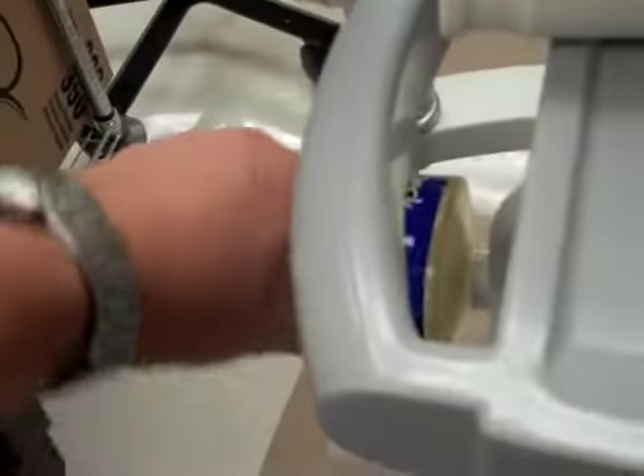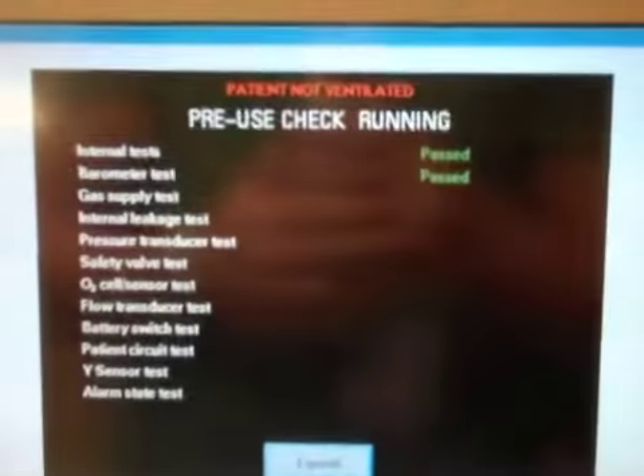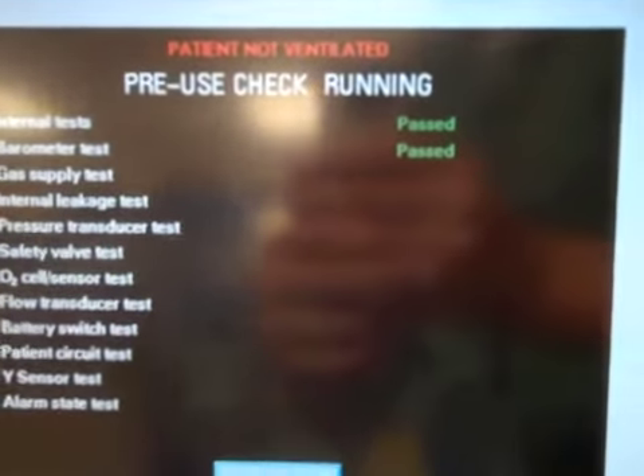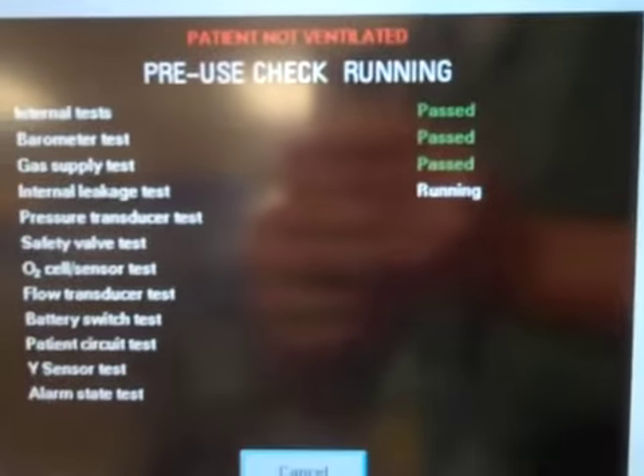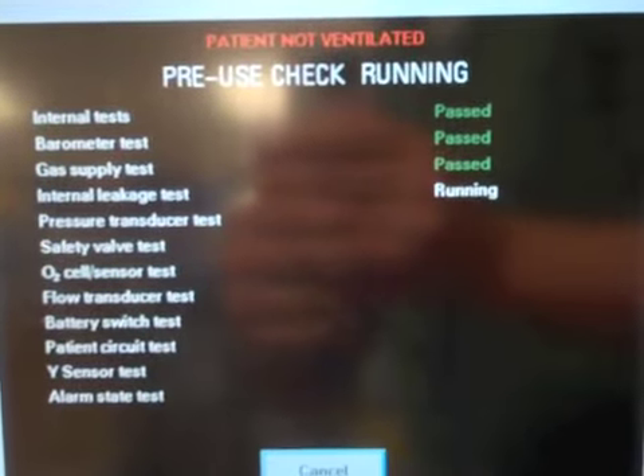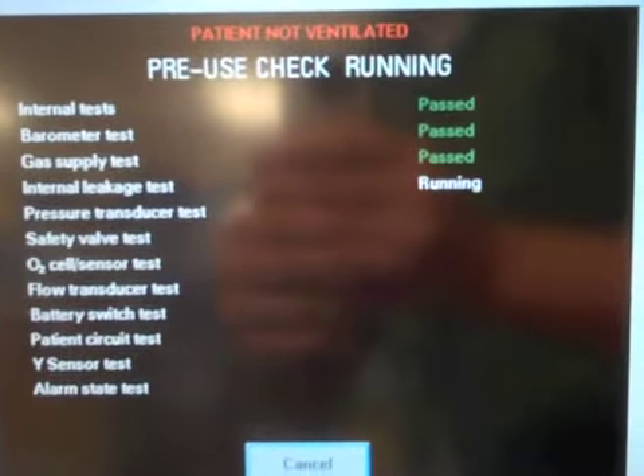This is the test tube that we use for the Servo-i, so I'm going to pop off the inspiratory and expiratory side just as it's asked. Connect my test tube up. Select OK, and away we go. So now it's doing a gas supply test, internal leakage test, pressure transducer test, safety valve test, O2 cell and sensor test, which it will fail. Again, because we're just testing this in the lab here and we don't actually have our oxygen piped into the machine right now. Flow transducer test, a battery switch test, patient circuit test, a Y sensor test.